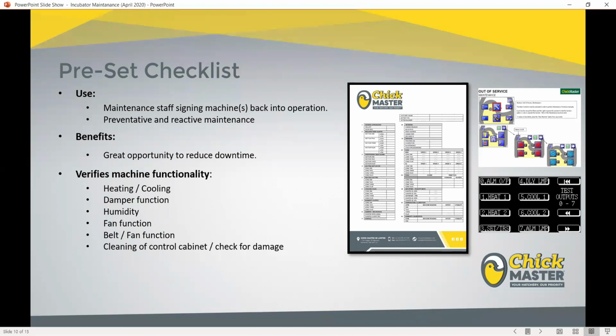Largely, it can be split into two different portions. You've got the condition of the machine and you've got the function of the machine. By function of the machine, what I'm referring to is the mechanical functions of the machine. So physically, what is it able to carry out? So this is where you're going to go through the testing screens and physically check the heating and the cooling. Do they activate? The damper function, does it open and close correctly into the correct tolerances? Does the humidity, if it's installed on the machine, activate? And does the fan alarm work? What's the condition, alignment, and tightness of the belt? It also gives you an opportunity to clean out the control cabinet whilst it's not live.